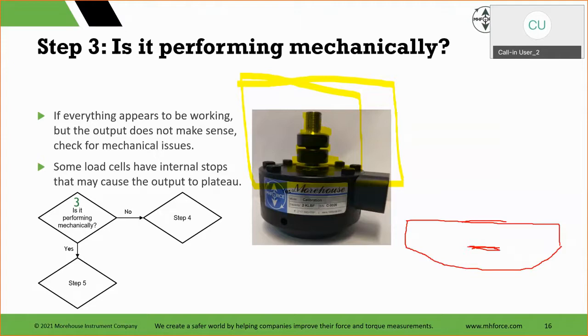Sometimes in manufacturing, someone threads it a little too far in, or they put it in and it needs to be turned down, and that's usually done from the other side of it. Sometimes it happens where, if this is the base, our threaded stop is way here. So if that correlates to this, our threaded stop is right here, and this is all thread. If that threaded stop is a little high, and this load cell output is 2 millivolts, sometimes it might bottom out at like 1.9998 and not get to the 2 millivolts.